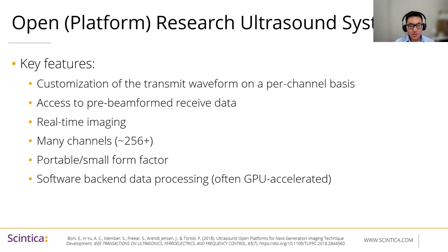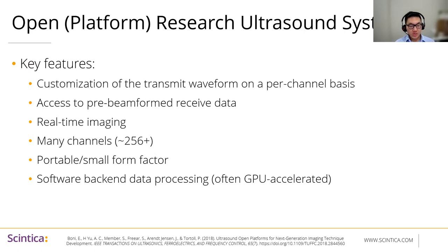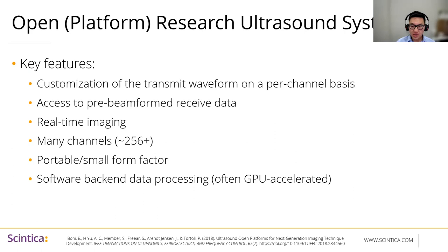The Prodigy fits right into this space as a commercial system, ready to use, very compact and transportable. Because this research field is now more established, we know what to expect. Key features include customization of the transmit waveform on a per-channel basis, access to pre-beamformed and beamformed received data, real-time imaging, typically 128 to 256 channels or more, portability, and very importantly a software back-end for data processing. This provides flexibility to run your own algorithms and is often accelerated with graphics cards, sitting in-between a CPU and dedicated FPGA hardware processing.